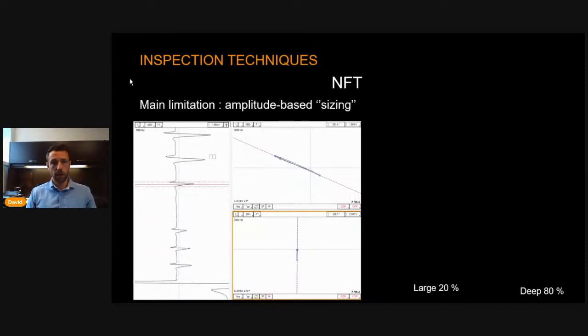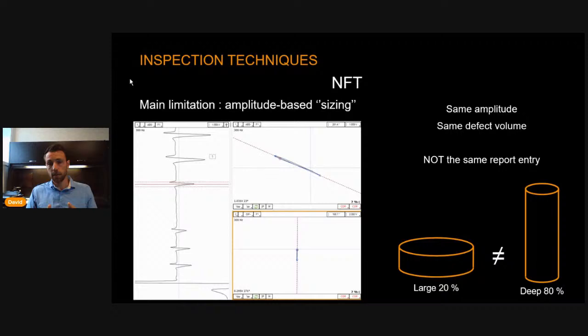However, the drawback, the limitation of NFT, is that it's only amplitude-based sizing. What does that mean? If we get an indication, we'll get a signal response. But if we compare two indications with the same signal response, we will get the same amplitude, and that means the defects have the same volume. That's what we're reading. But you know that the same volume doesn't mean the same report entry. A large 20% defect gets the same response as a deep 80% defect. It's easy to understand which one you want to make sure you add to your report: the deep 80%. You want to make sure that you see those indications. So this is what is difficult with NFT: even though there's a large amplitude, is it because it is a large defect or is it a deep defect?